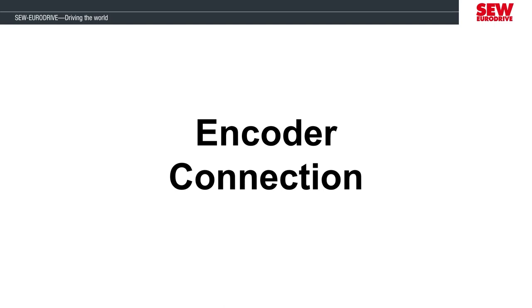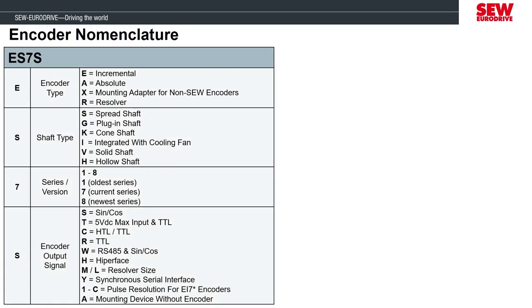Let's start by talking about our encoder nomenclature and how it's connected. We have a wide selection of encoders to choose from, and our encoders follow a four-character naming style. The first letter tells what type of encoder it is, such as incremental, absolute, or resolver. The next letter is the type of output shaft the encoder uses, which varies based on how the encoder connects to the rotor. The number represents the series: the one series was used on older DT and DV motors, the seven series on DR motors, and this year we are releasing the eight series encoders for DR motors.